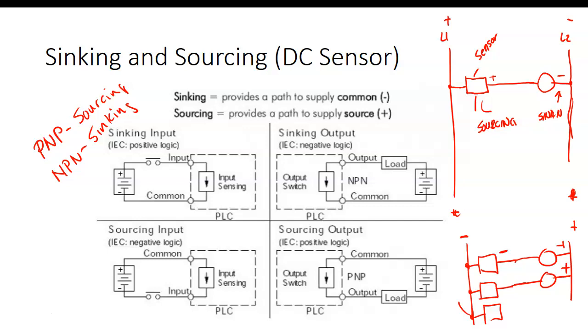So you need to make it sense. When you buy these DC sensors, they're going to be specified as PNP or NPN. So you need to know what your control system requires. If it's requiring a negative, you're going to buy a sinking sensor. If your control requires a positive, you better buy a sourcing sensor. So a sourcing sensor would be specified as a PNP, and a negative sensor would be specified as an NPN. Everybody okay there?